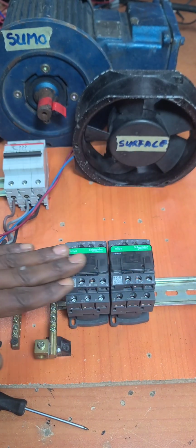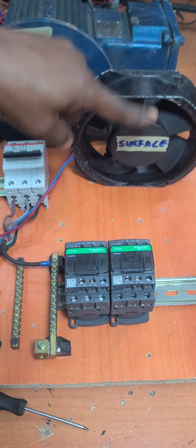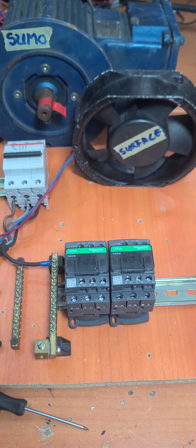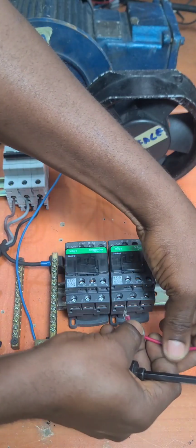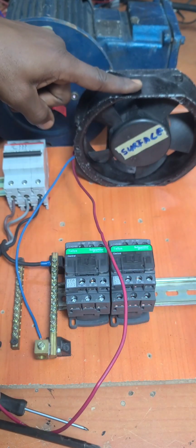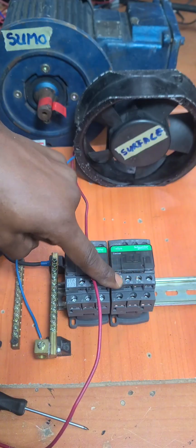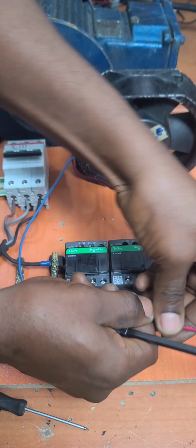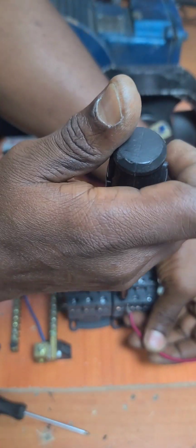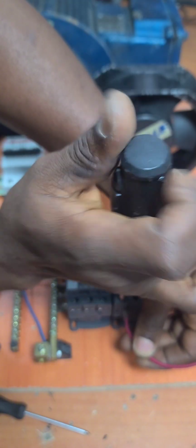We're going to attach it this way. So the first thing we're going to do is to connect this one to this contactor. So we're going to take this one and connect to the output of this contactor. Let us use this one. This one is a single phase, so we're going to just make use of single phase here on this contactor. So to do that, we need to slack out on this terminal, T1, and then insert this wire carefully, and then we'll lock it up.